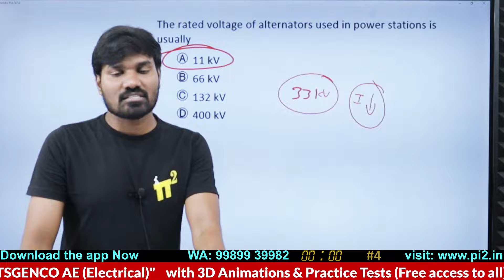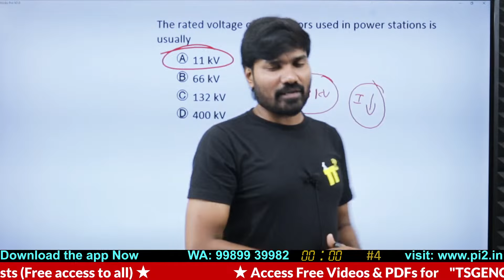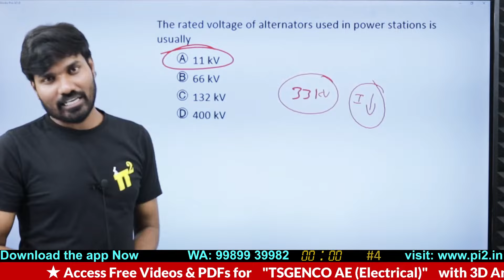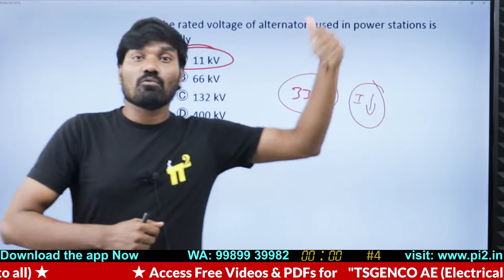Wow man, most people have answered it very well. Yes, you can increase voltage to 33 kilovolts also, but insulation is one of the key aspects. If it's a current, a copper conductor is there, that will nicely carry the current, it's okay. But when it comes to insulation, you see, transmission line towers have two conductors spaced too distantly - some meters distance between two conductors - because when you increase the voltage, insulation is one of the biggest problems. That's the reason why underground cables will not go for high voltage.